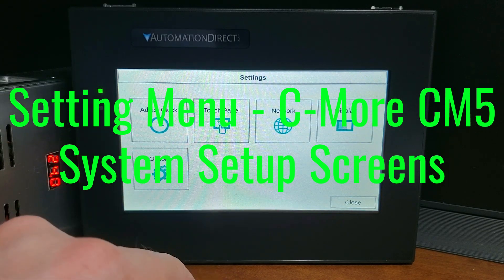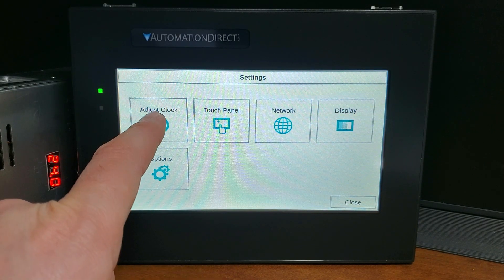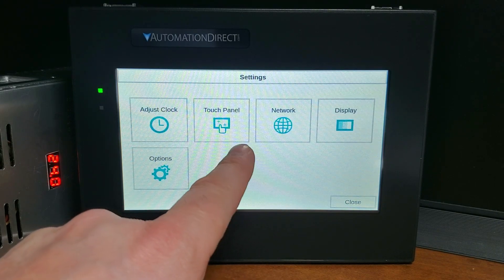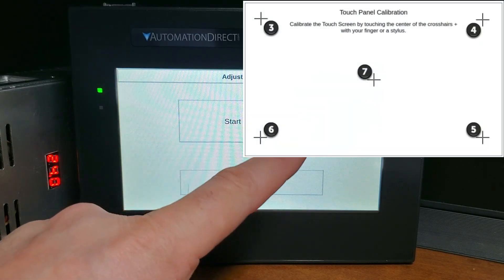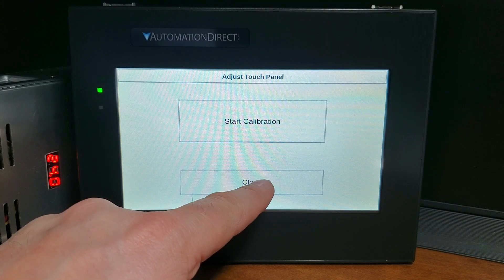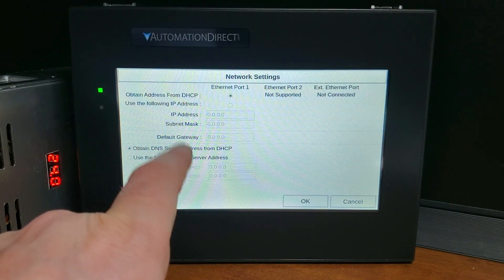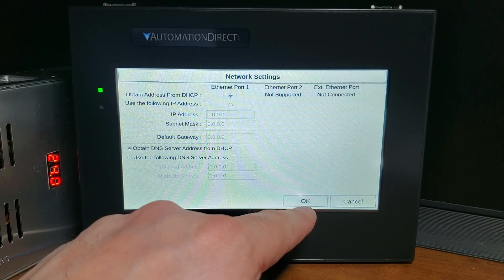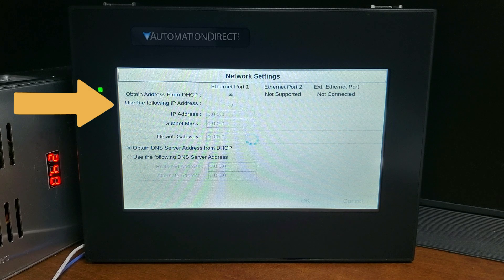Settings menu for the C-more setup screens. Adjust clock: this setting will help you adjust the real-time clock on our CM5 HMI screen. Adjust panel: we can start the calibration procedure of the HMI panel, which will automatically start when we have a new panel or if we restore from factory default. Network settings: IP address settings allow us to set up the Ethernet IP settings. When first selected, DHCP is enabled as a default and all other selections are dimmed. When DHCP is unavailable, the 'use following IP address' setting is selected via the radio button, and you can change the IP address as you wish.